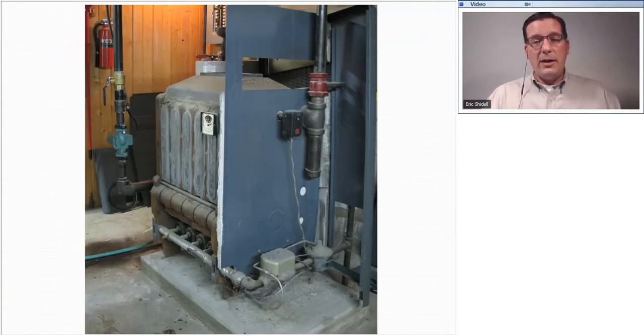Now, this one right here that we looked at is a hot water boiler. And it's gone through some changes over the years. It's wearing a new pump right here. I see some new pieces of pipe here for some reason. You can see this section here looks a little older than this section here does. Brand new modern ball valve. So there's been some repairs on this system over the years.